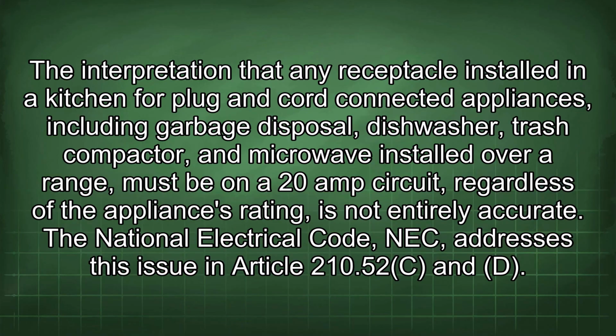The interpretation that any receptacle installed in a kitchen for plug-and-cord-connected appliances, including garbage disposal, dishwasher, trash compactor, and microwave installed over a range, must be on a 20 amp circuit, regardless of the appliance's rating, is not entirely accurate. The National Electrical Code, NEC, addresses this issue in Article 210.52c and d.